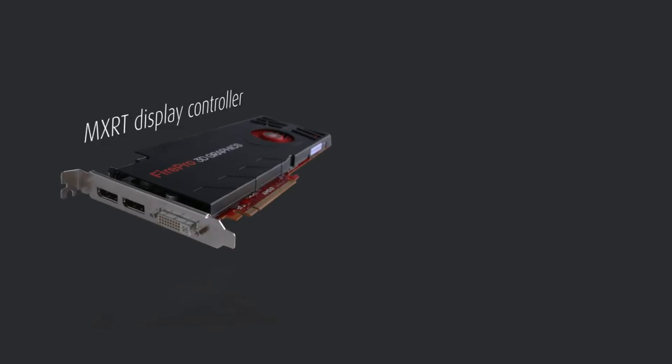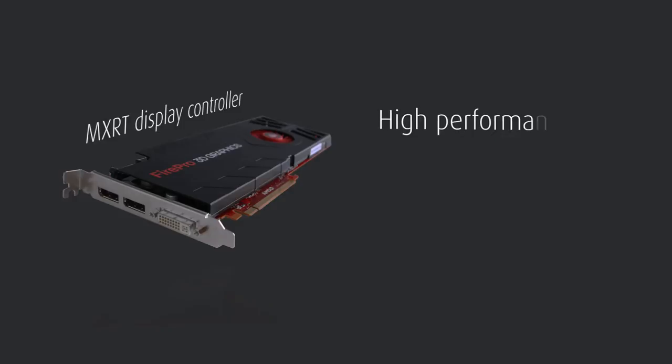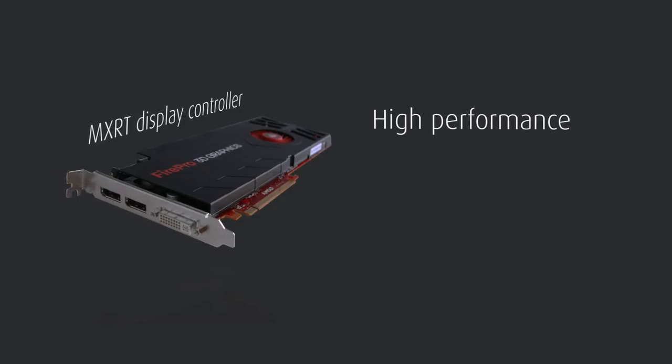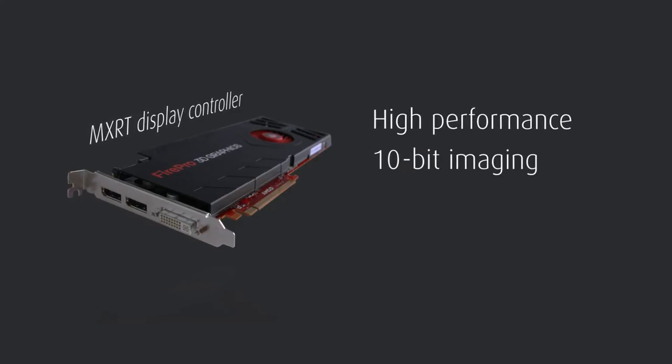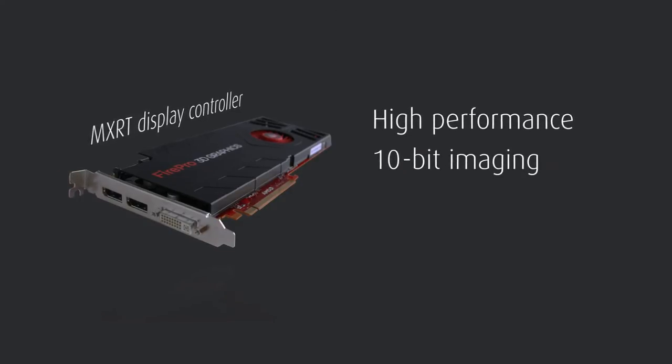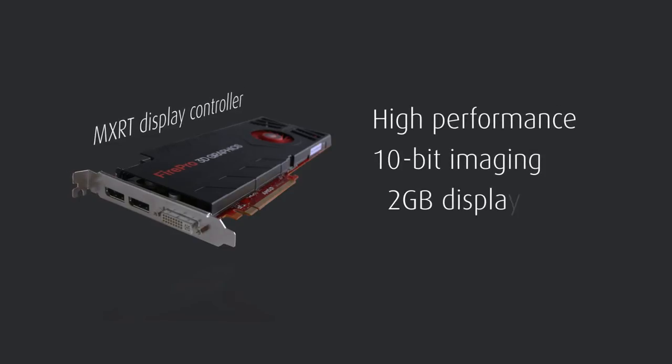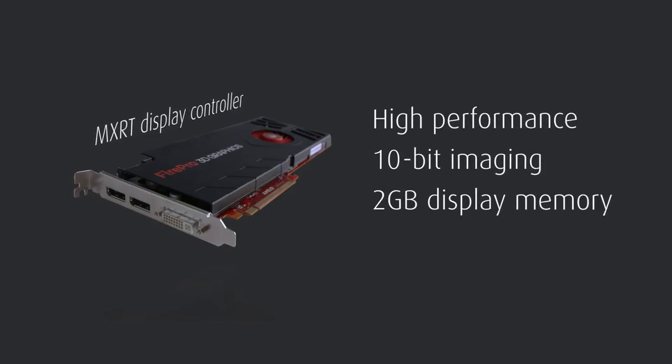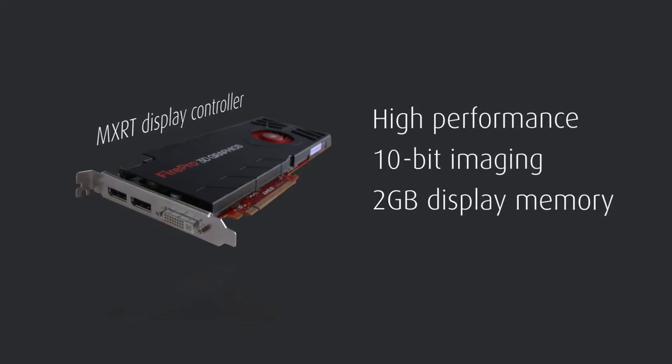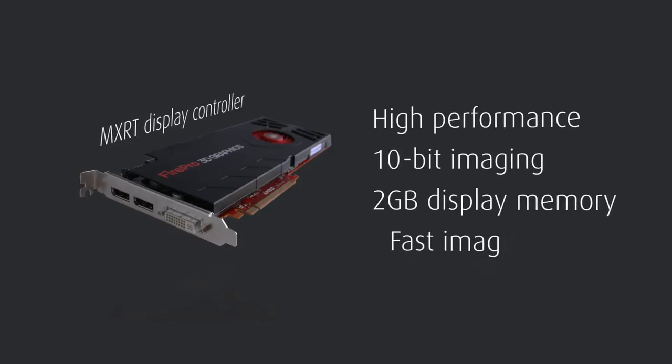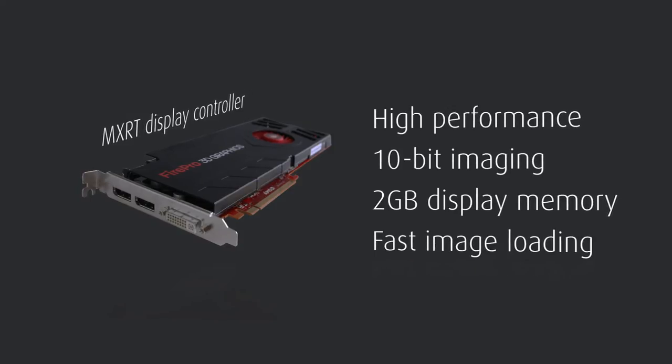Secondly, handling such multi-frame studies requires a high-performance display controller. Rapid Frame is combined with a powerful display controller that has up to 2 GB of memory for holding large stacks of images, so that large studies can be displayed rapidly.